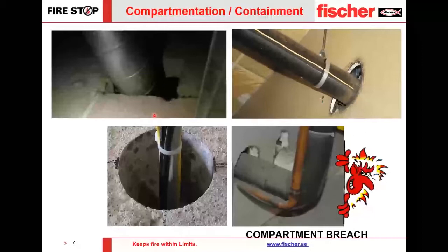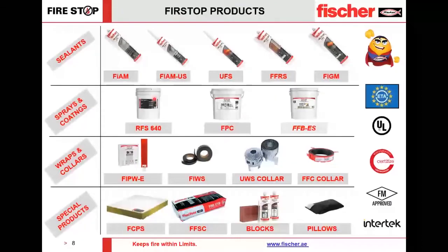These breaches completely compromise the fire life safety strategy of a building, putting all occupants at risk. In a typical image you can see several types of penetrants that have breached fire-resisting assemblies. Since there are several types of breaches, a range of products is required to treat them. fischer, as a manufacturer, has Firestop products to address all usual and unexpected situations on a project site. These products are either sealants, sprays and coatings, wraps and collars, or special products.